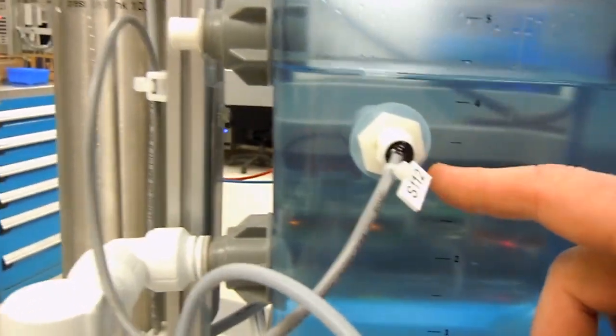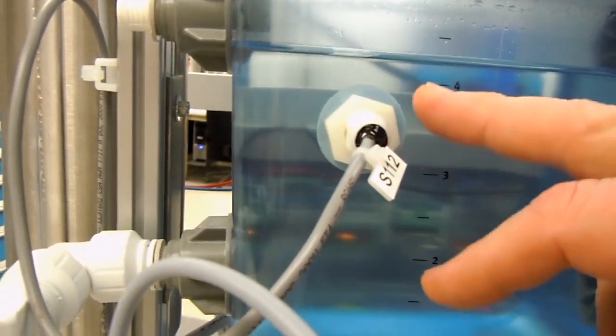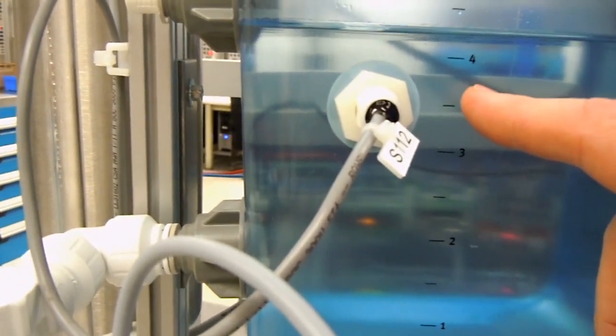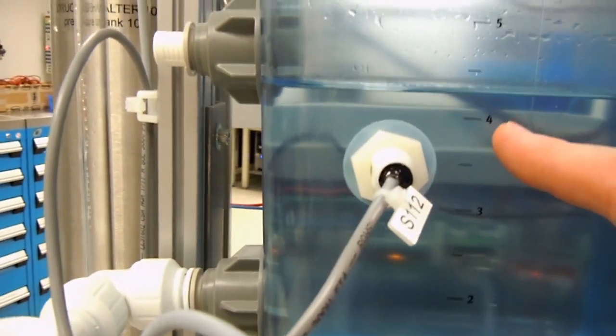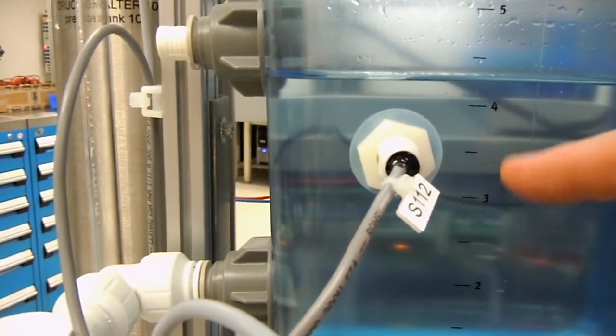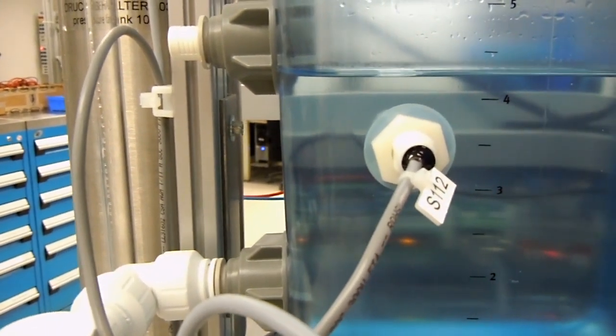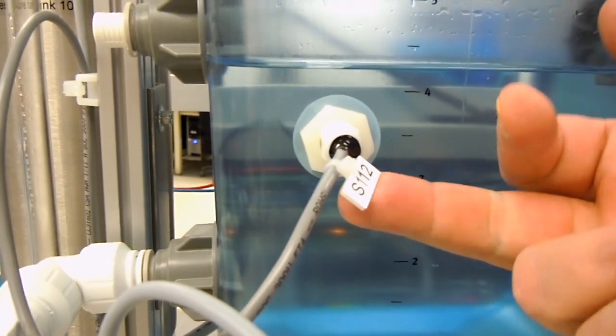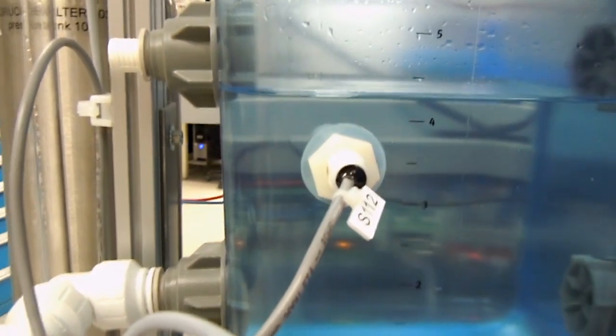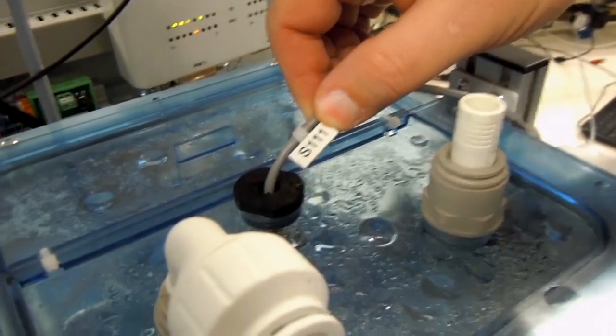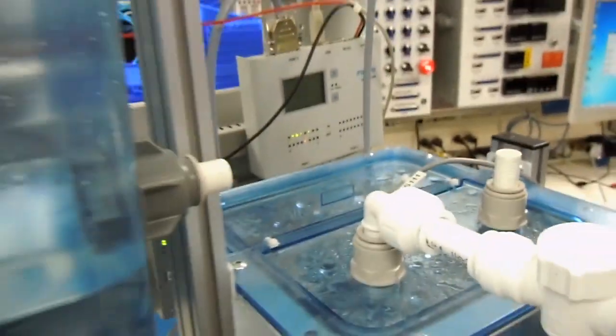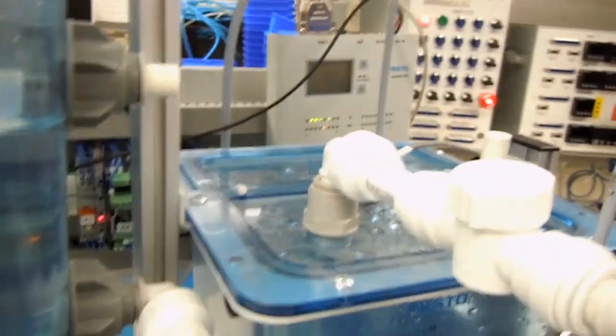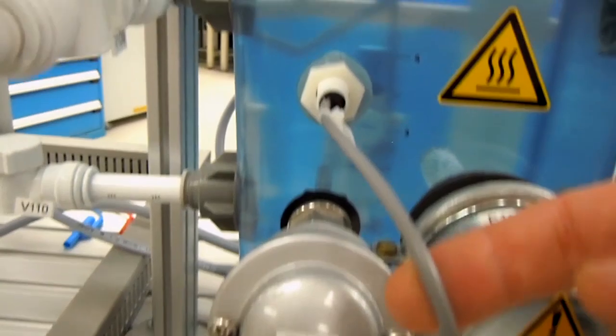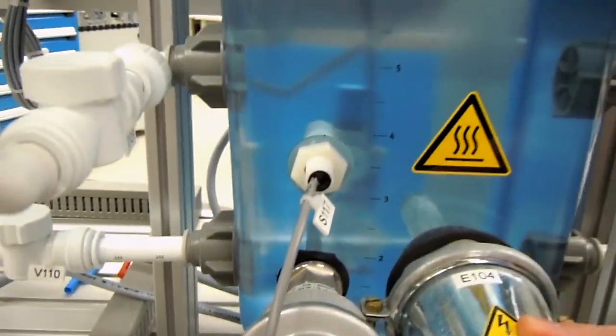Over on the upper tank, there's a float on the side. Right now it's buoyant or floating. So the plastic piece inside the tank is actually lighter or less dense than the water in the tank. So when it rises up, it closes a reed switch and then sends a signal to the computer, and that one's called S112. The one on the top of the tank is S111. Okay, so those are the 3 floats. 2 of them are electrical signals. S117 is a safety for the heater.